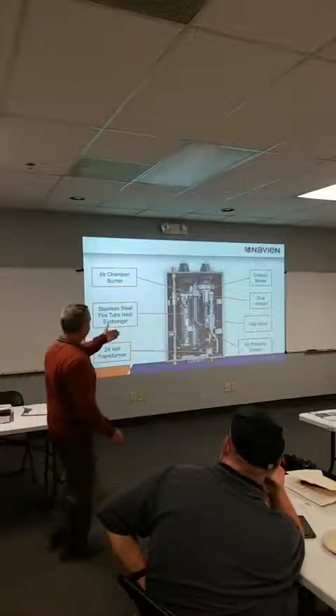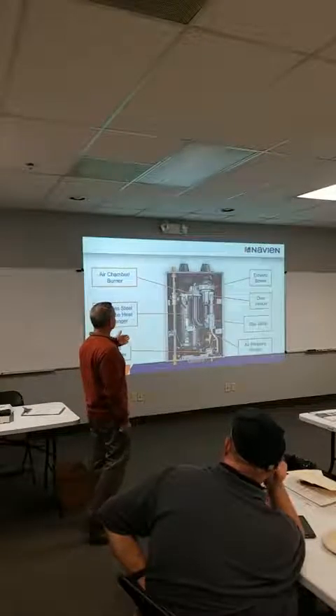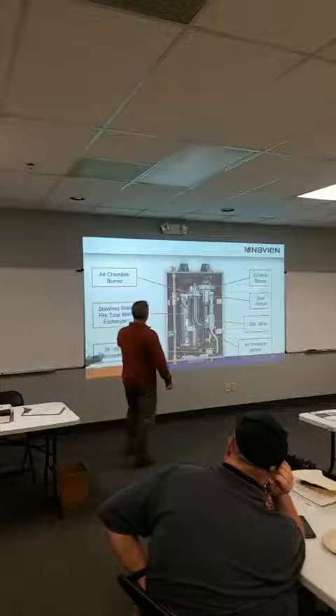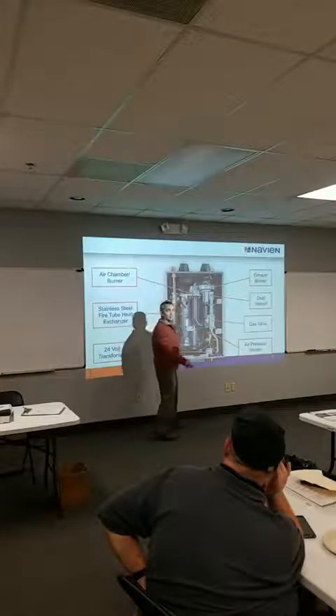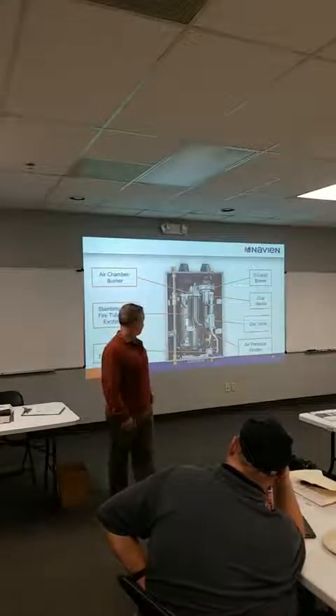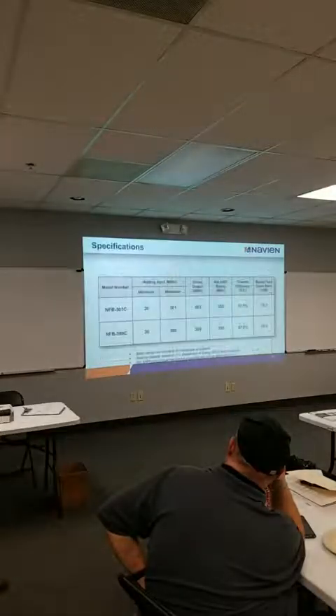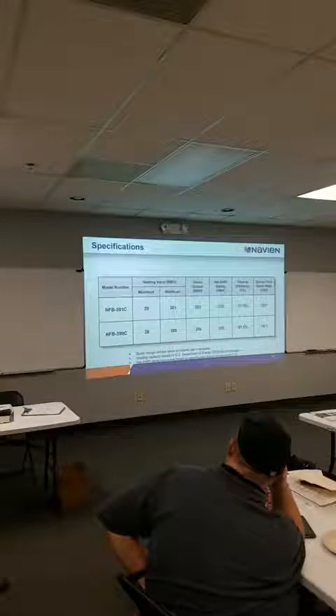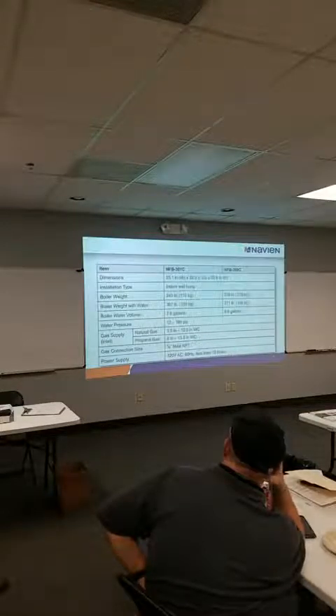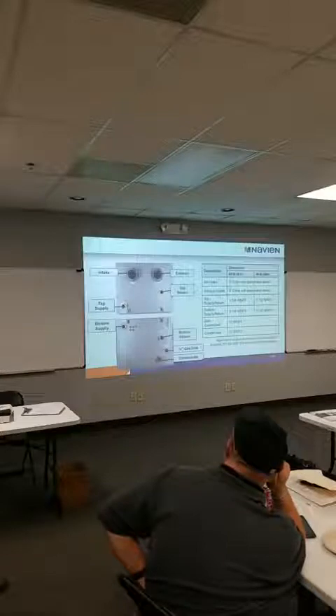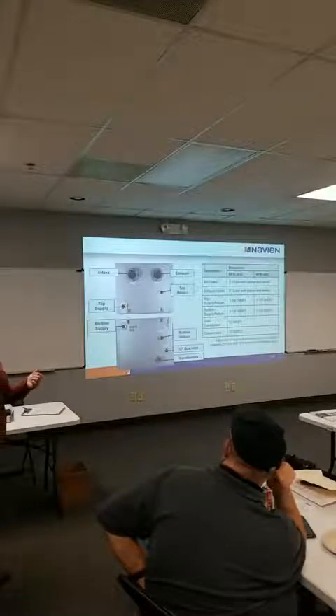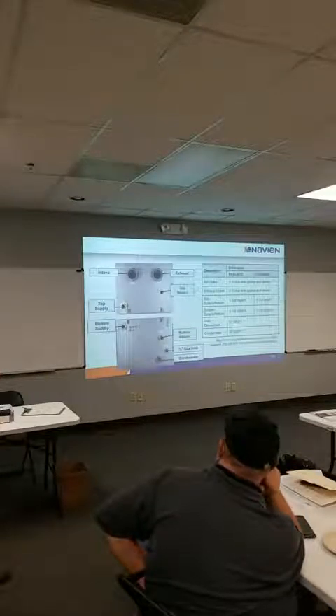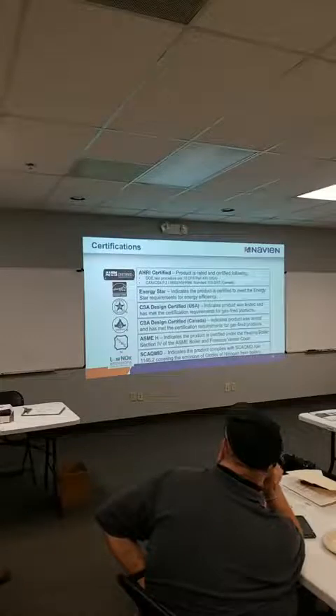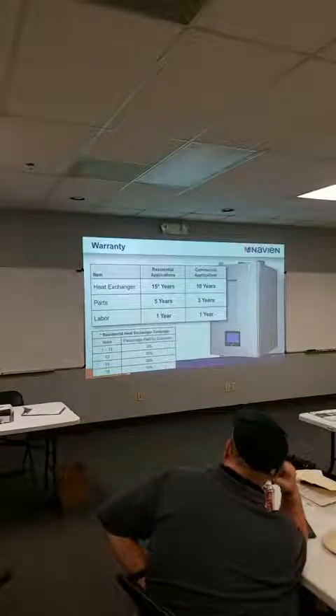So, gas valve again, similar gas valve right in front. The exhaust blower's a little beefier. But again, you can see this is all accessible. If you need to get into that burner chamber, you can do it without taking a bunch of stuff apart. Here's your basic ratings. They're both 15:1. It is kind of heavy. So you got 1.25 inch, 1.5 connections on the bottom. This is 3/4 inch gas minimum, so you can't run 1/2 inch gas to this unit. So there's all your approvals. There's your warranty, basically the same.